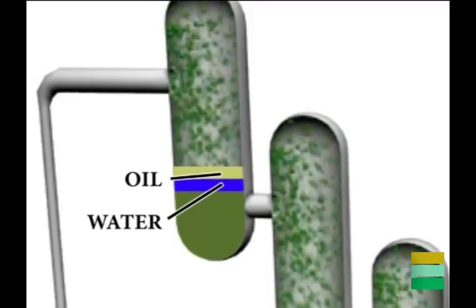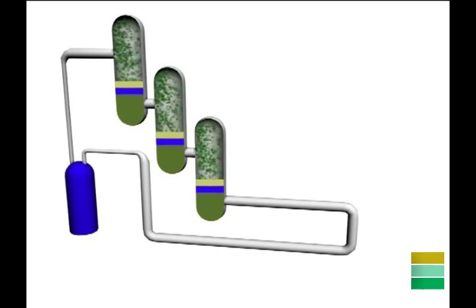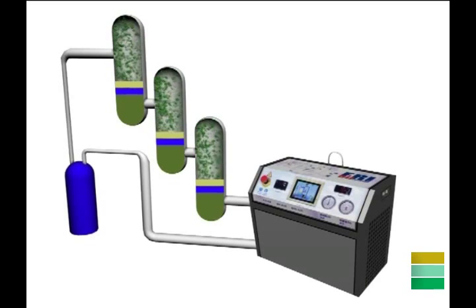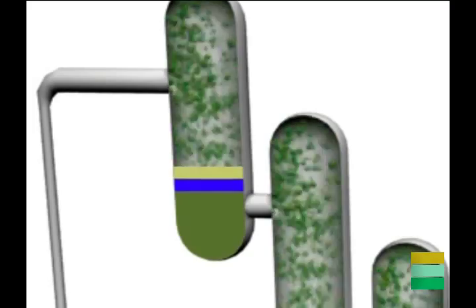The cleaning refrigerant will then enter at a significant pressure differential, causing it to drag the remaining oil from the tube and component inside surfaces or walls. Once the system pressure is balanced, we can connect the free oil system to the circuit to be cleaned and, through cycles of injection and suction, push the cleaning refrigerant through the circuit until it arrives at the free oil unit in a liquid state. This will tell us that all the siphons of the refrigerating circuit are full of liquid refrigerant and that the lower density products are on top of the refrigerant and at the spillways.